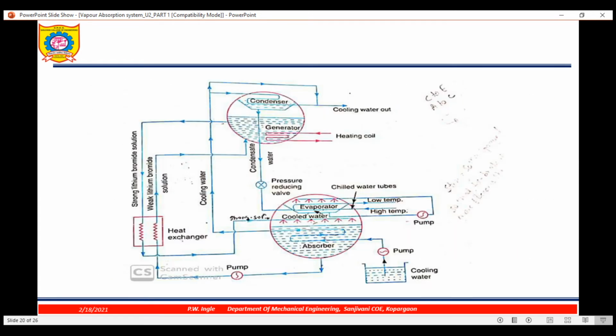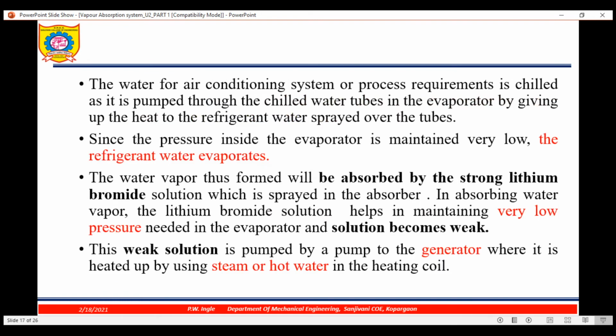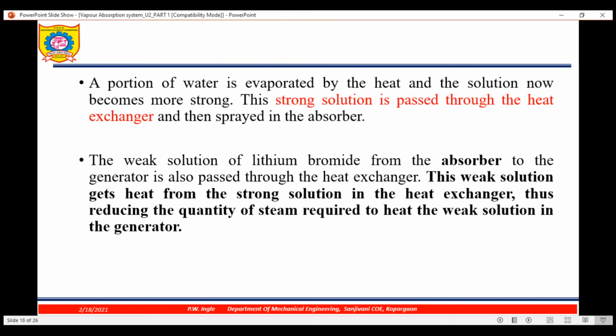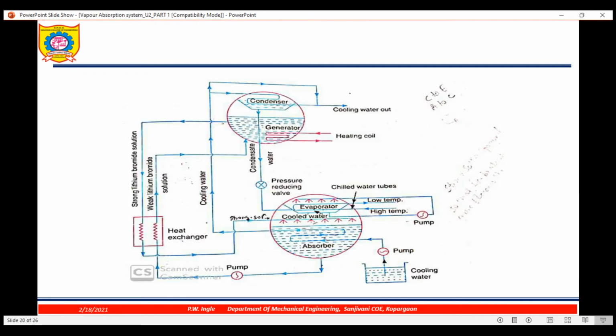Now whatever weak solution you have got here, how are we getting the weak solution? LiBr, which acts as an absorbent, will absorb the refrigerant in vapor condition, that is water. So it will be pumped back to the generator. Now next, this weak solution is pumped by a pump to the generator where it is heated by steam or hot water in the heating coil. Again we'll see the diagram. In the generator it will be heated by steam or the heating coil.